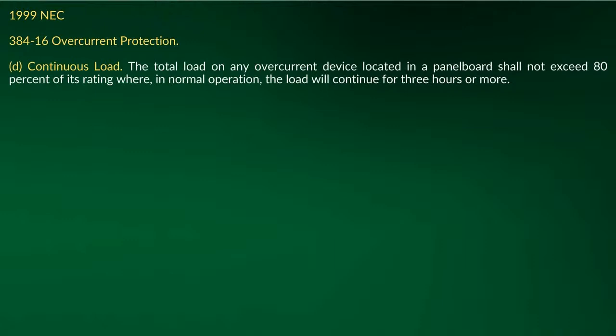Now, what used to happen, and the reason that they took this out, was because people would go look, and I'll show you these sections in a minute, at 210.19(A) or 215.2(A), and they would take the continuous load at 125% and the non-continuous load at 100%. Then they get the amperage, and they would take the breaker and then take 80% of that breaker to protect that load, and that's not what you did. That's where the problem came in. I can't even remember, somebody actually had it in one of their publications, showing to do that, and they said no, that's not going to work. So they took that out.